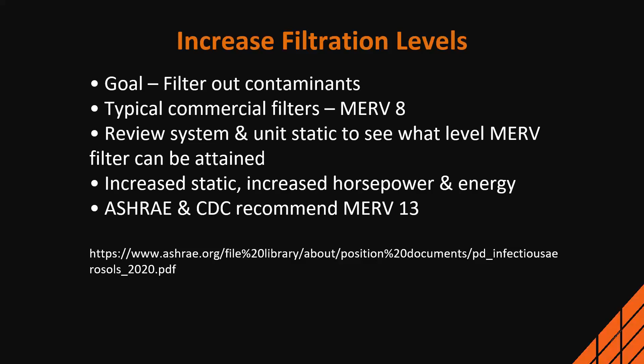ASHRAE and CDC both made initial recommendations of MERV 13. The way they've made that recommendation, though, is that's kind of a goal line, but they both say if you can't get to MERV 13, go as far as you can. So if you can get to MERV 11, we'll go to MERV 11. It's better than your MERV 8. If you can get past it and get to MERV 14 or 15, well, go ahead, go to 14 or 15 because it's going to capture even more. So they give you the MERV 13 goal, but the farther you can get, the better off you are. And this is kind of why they gave it to you.